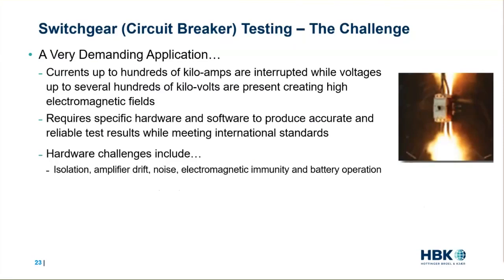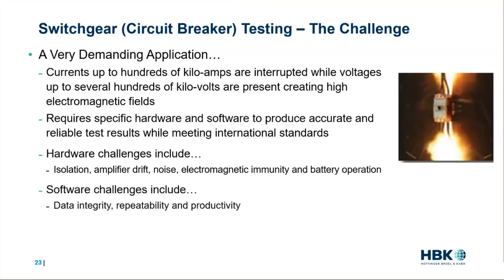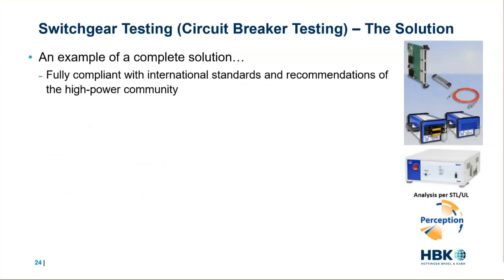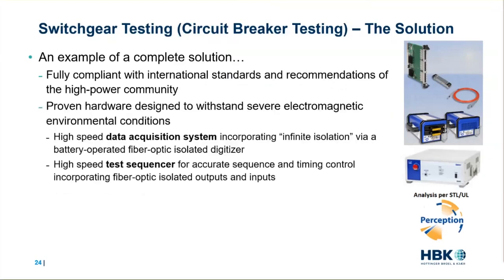Now, some of the hardware challenges include isolation, amplifier drift, noise, electromagnetic immunity, and battery operation. There are even software challenges that include data integrity, repeatability, and productivity. Now, here's an example of a complete solution which is fully compliant with international standards and recommendations of the high power community. We have proven hardware designed to withstand severe electromagnetic and environmental conditions. There's a high-speed data acquisition system incorporating technically infinite isolation via a battery-operated fiber optic isolated digitizer. There's also a high-speed test sequencer for accurate sequence and timing control, incorporating fiber optic isolated outputs and inputs. We'll talk more about these pieces in just a moment.